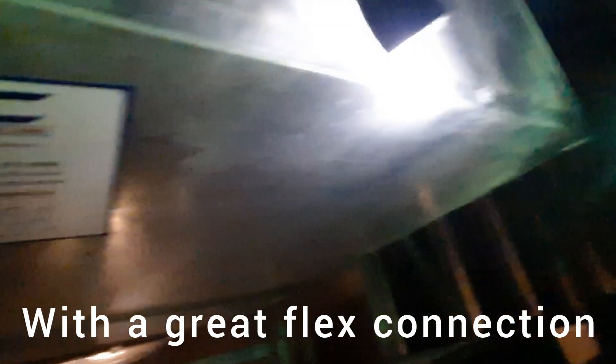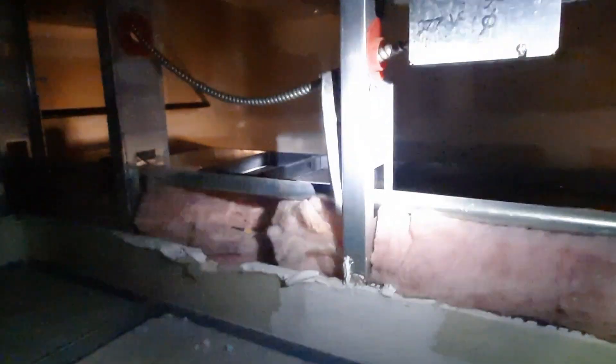As you can see it is a tight space. This is our box. Damper is right inside of here. We have a blower motor, so blower motor comes on when it calls for heat. Heat strips are right there, can't get to because that's a drywall assembly. You can see I was standing right there yesterday, but I got an amp draw on the heater and verified it worked. There's an air flow switch in there that connects to said blower motor over here, and that allows the heat to come on. So basically I've got to tear the bottom off of this unit, get a couple screws out, drop the bottom down, be able to get to that actuator.